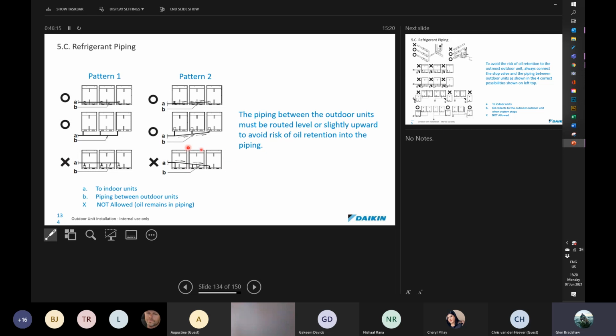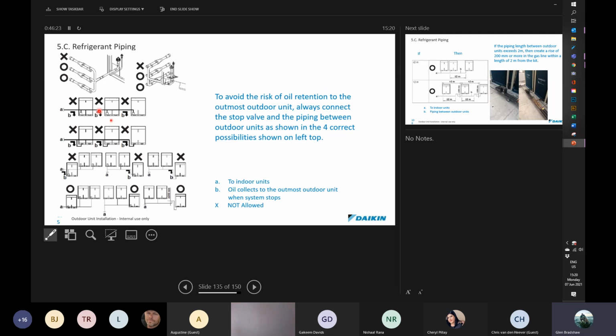Make sure that you're not installing along these lines over here. There's a couple more of them. Over here, I've had this question before: are these three ref nets going to different condensers? No. What this is showing you is that each of these ref nets connects into the same condenser. It shows that if you place this ref net above the service valves, it is not allowed. If it is horizontal or level with the service valves, it is allowed, and below is also allowed. There's just another view of it. That is why you see the three ref nets there, not because it's a system with multiple condensers. Don't see it like that, because if it was multiple condensers, you would only have 2 ref nets, because the maximum number of units to be connected is 3. That's just giving you an idea of where you can place them.